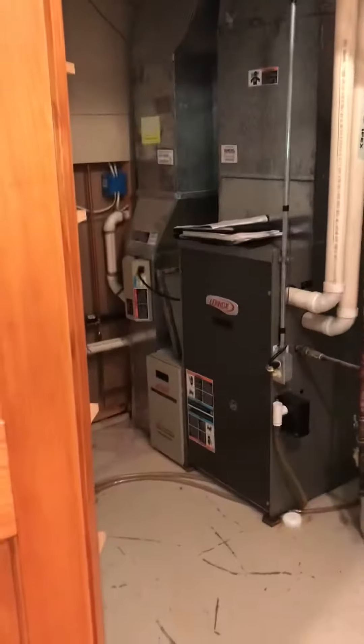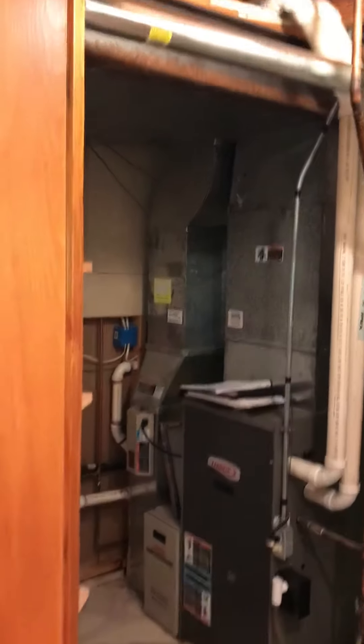We're in a basement situation and we're focused on AC coil replacement. Everything's located in a utility closet. We're going to give the option to do the furnace at the same time. We set up high efficiency — you can see the piping that's making its way out to the outside. There is some ventilation, a pass-through ventilation, because the water heater is still 80% efficiency.